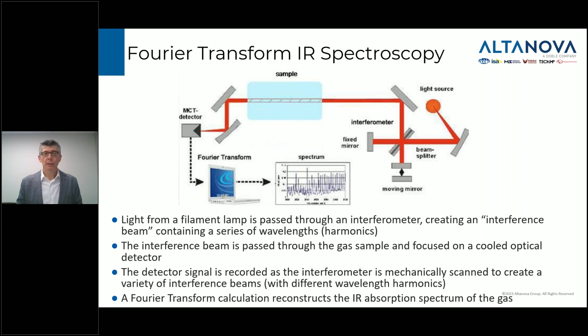And it turns out, smart people who developed this technique figured out that if you perform a Fourier transform calculation on the data accumulated with this type of optical configuration, you can recreate with good resolution the infrared absorption spectrum of all the gases in the sample. So it's a very clever technique and quite new on our market. I think the biggest advantage is that we accumulate a much more complete spectrum. There's a lot more spectral information you can gather with this approach. That's helpful if there are interfering compounds in the oil: you can do a better job of identifying them in the spectrum and compensating for them, pulling them out of the data and getting good measurements of the target gases for the DGA.